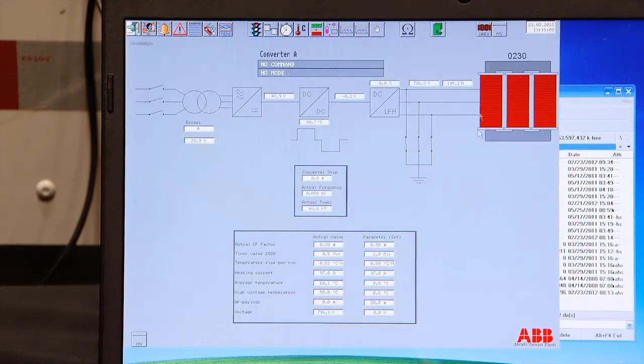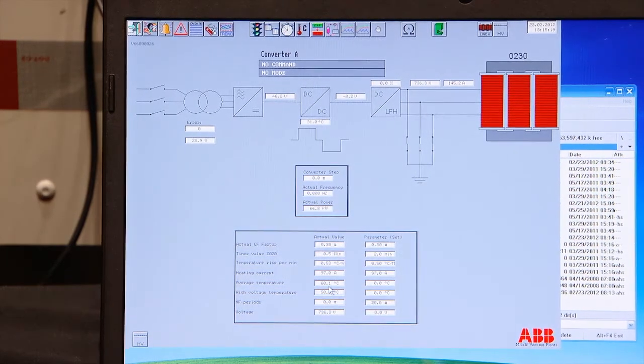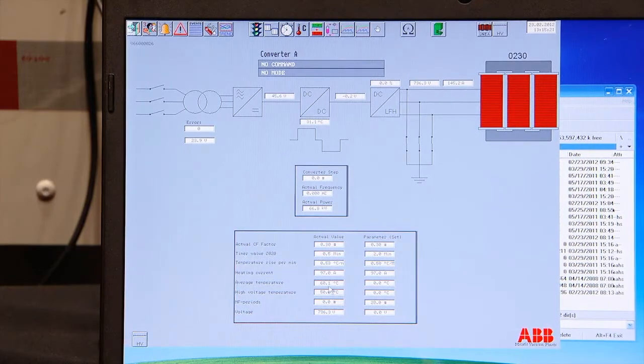Converter has stopped. Average temperature at 60 degrees. That's the time when you want to do the high voltage measurement. So he will now make another average measurement reading for the temperature. Then he will go into high voltage measurement to see the temperature difference between the windings.